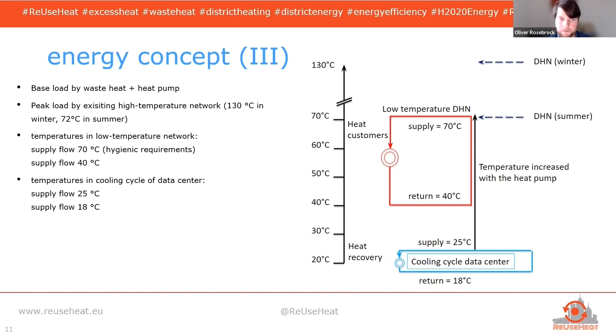If we think about how it is done in detail, this is more or less a very simple schematic. We have the data center operator. The data center operator has a heat exchanger, and the heat exchanger is connected with the evaporator of the heat pump. Then we have the heat storage. Then we have the high temperature district heating network, which has a heat exchanger with the heat storage. And we have the low temperature district heating network covered from the heat storage inside this plant.